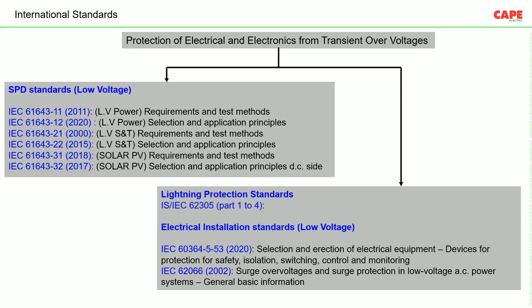Now the first two standards, 61643 part 11 and part 12, are accepted as they are by our IS also, with the name IS 16463 part 11 and part 12. The upper two standards have been accepted by India also. Apart from that, as you know, SPD is also an integral part of a lightning protection system. It is also called the internal lightning protection system. So IS 62305 or IEC 62305 also discusses the same thing, SPDs. Again, with respect to electrical installation, IEC 60364 part 5, 53 discusses how to install an SPD in an electrical system. That means it says how to use an SPD in electrical wiring safely.